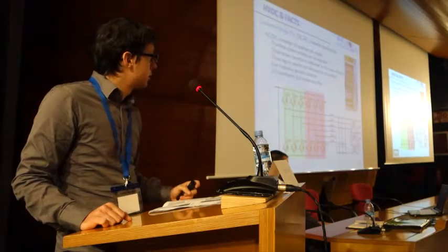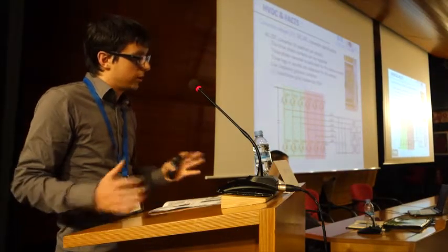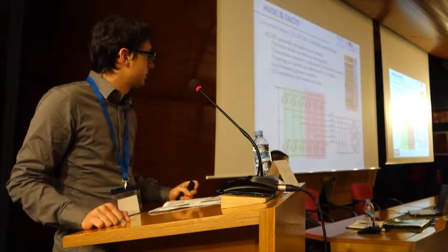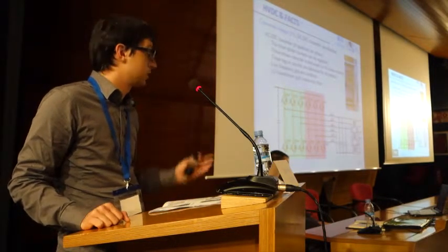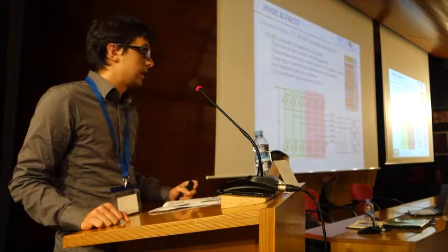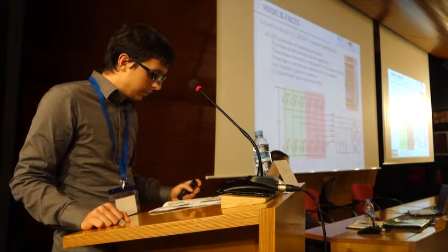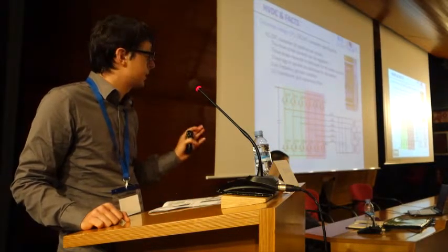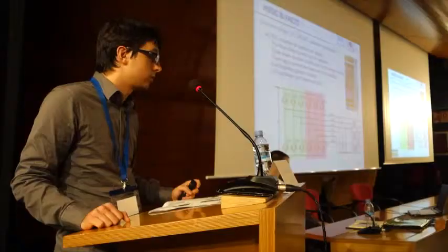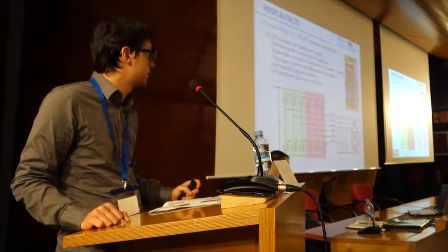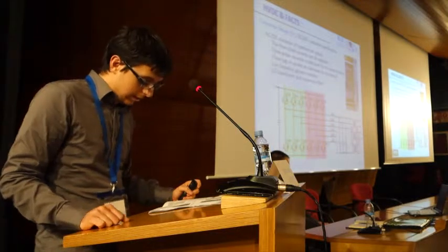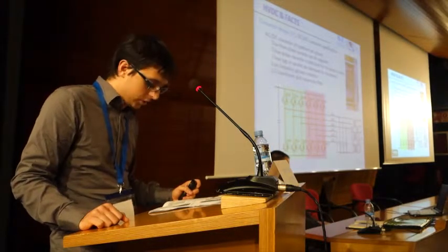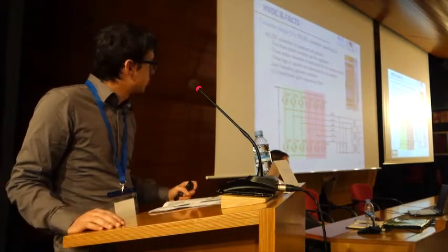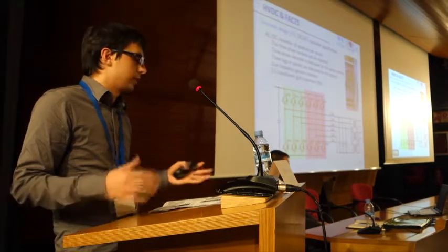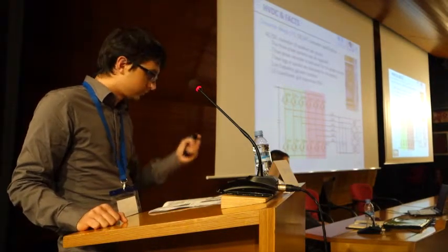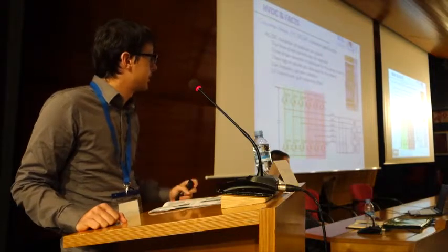This DC-AC converter is connected to the microgrid or the grid, depending on the state of the main switch that allows interconnecting the systems, through an LCL filter. Basically, it's important to remark also that the capacitors are there in terms of control, not in terms of filtering. And we add this low-frequency galvanic isolation to make it more compatible with any kind of neutral grounding system that we can have on the AC side.